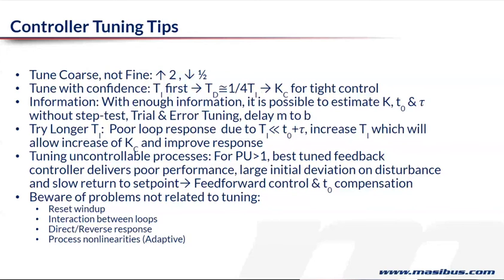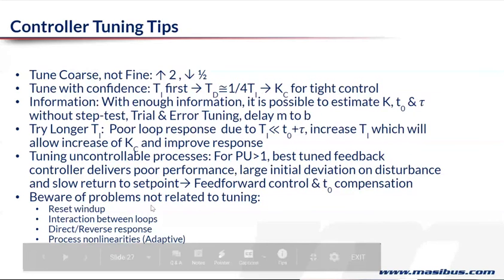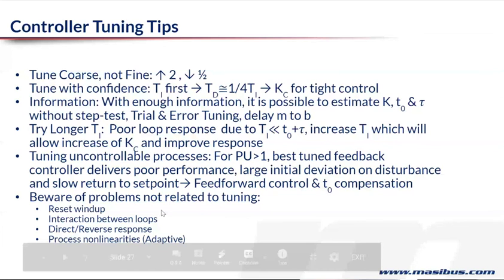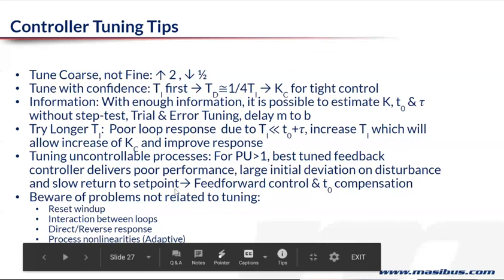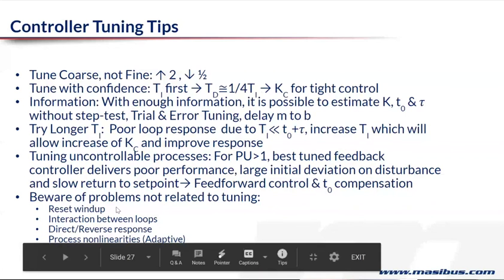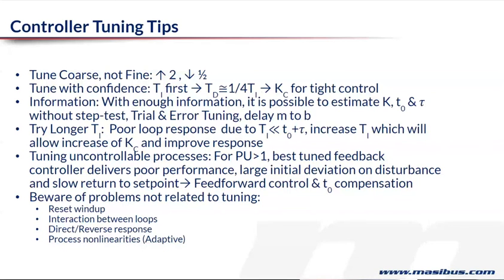Sometimes you have to beware of problems which are not related to your tuning, and if you go about retuning your controller because of those problems, you will be creating a problem when there is no problem. We just talked about the reset windup, where the controller's 100% delivered flow is not matching your PID controller's 100% output, and then you end up with a reset windup phenomenon.